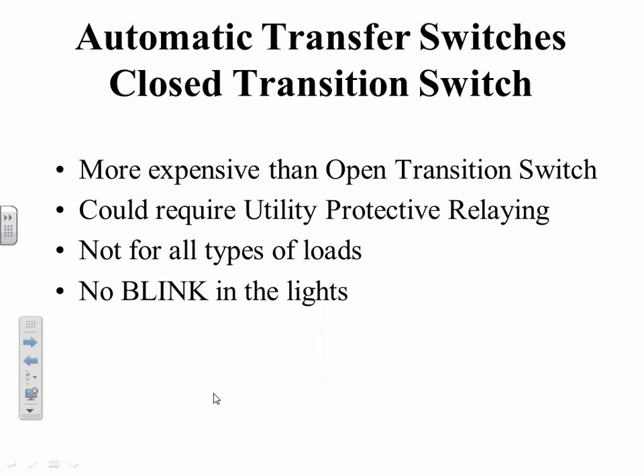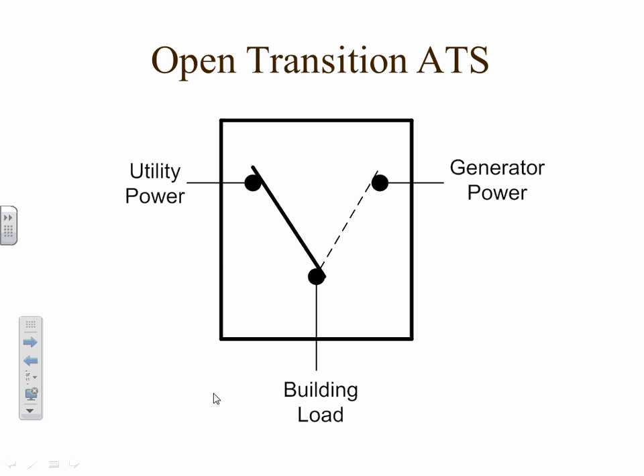Okay, moving on. Another type of transfer switch that you're going to see is what they call a closed transition switch. This is more expensive than the open transition, simply because it's a little more sophisticated. Going back, looking at this, these are my drawings, but a lot of engineers use the same type of drawing. When it flops between utility power and generator power, I call this point here for the load the pivot point. So this is what's pivoting, is this point, and that's the load.